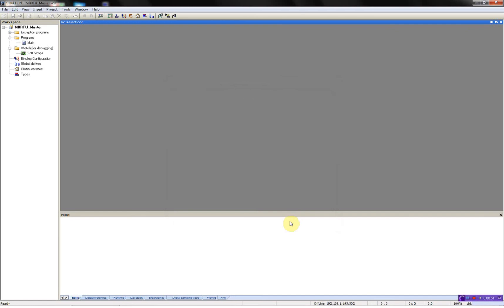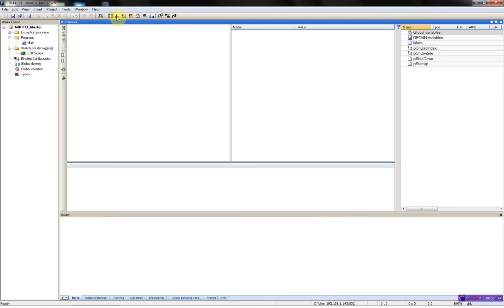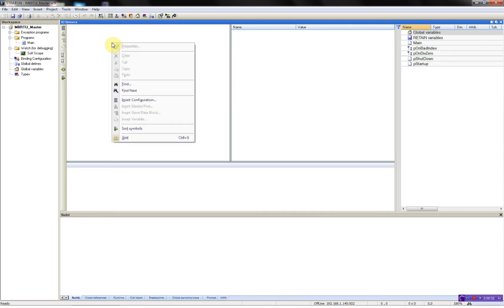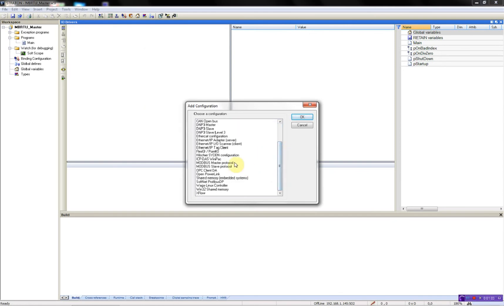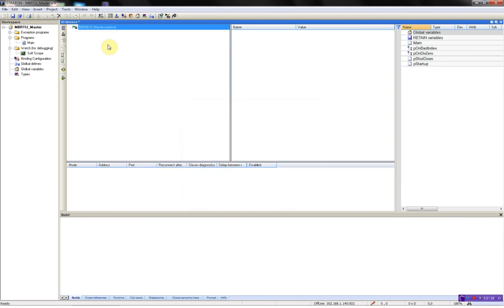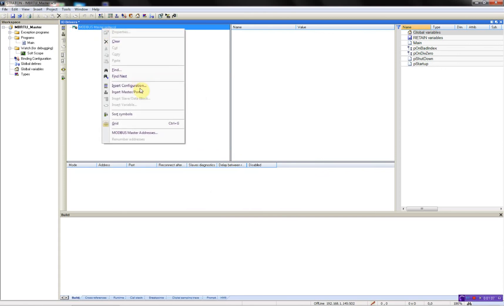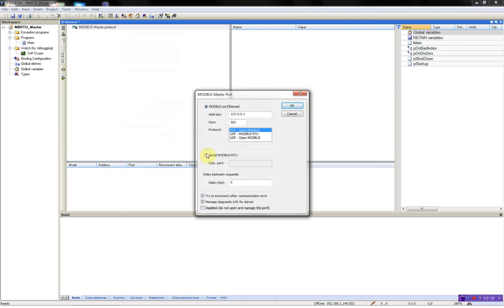Then I will need to configure the Modbus master driver. I have to open the fieldbus configurator and right-click to add a configuration — we'll find the Modbus master protocol. Then I need to add the master port; in this case we'll be using serial communication. I have to put in my COM port configuration: COM2 running 9600, non-parity, 8 data bits and one stop bit. Then OK.